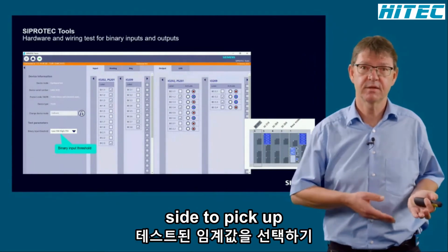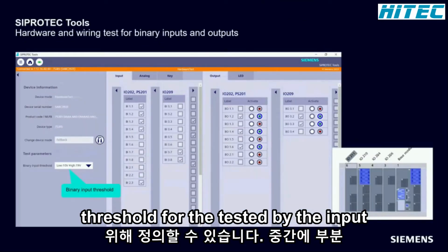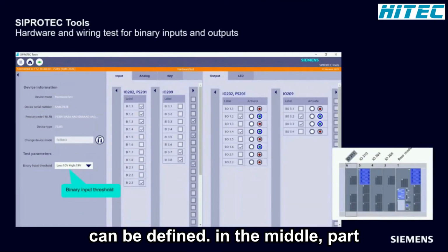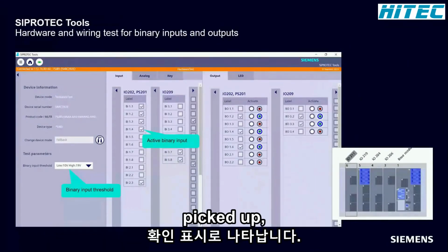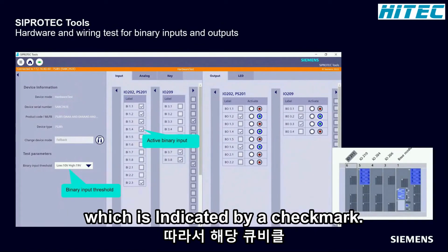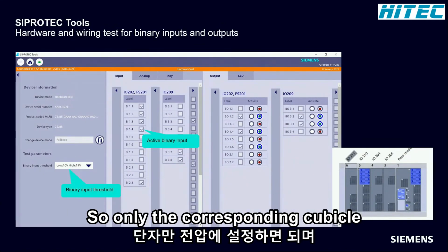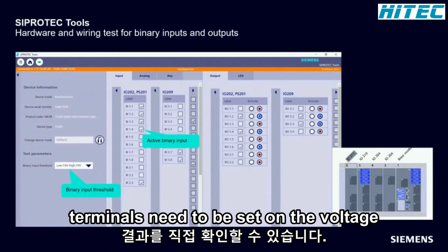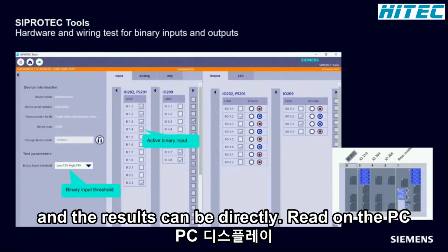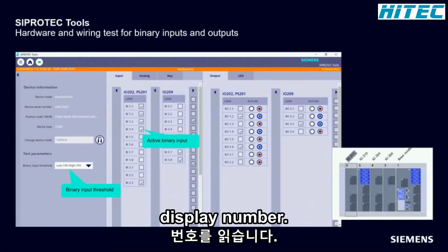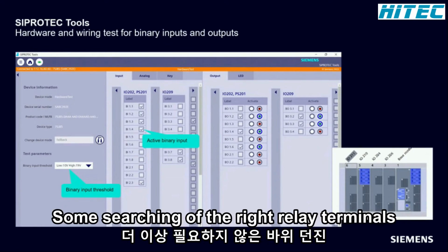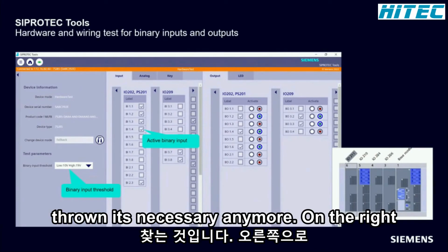On the left-hand side, the pickup threshold for the tested binary input can be defined. In the middle part, we see which binary input has picked up, which is indicated by a check mark. So only the corresponding cubicle terminals need to be set under voltage, and the result can be directly read on the PC display. No cumbersome searching of the right relay terminals, which is error-prone, is necessary anymore.